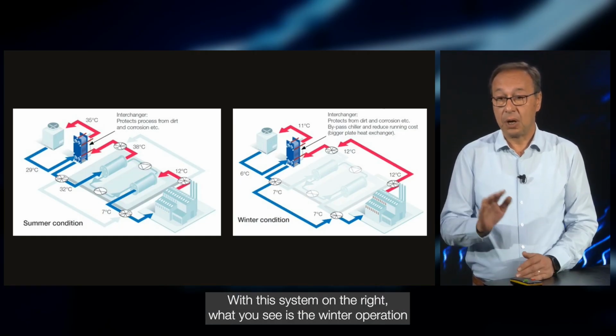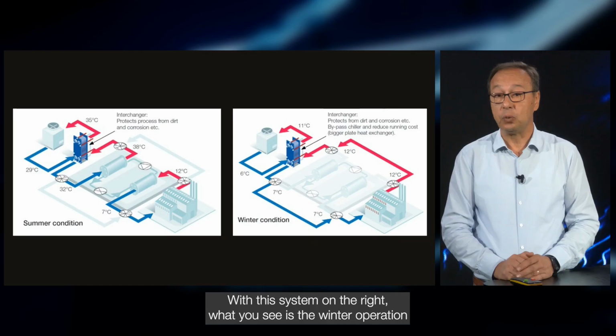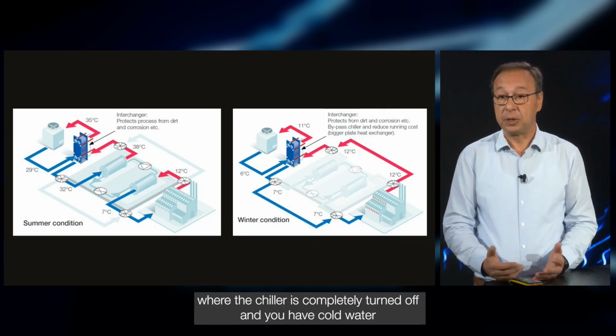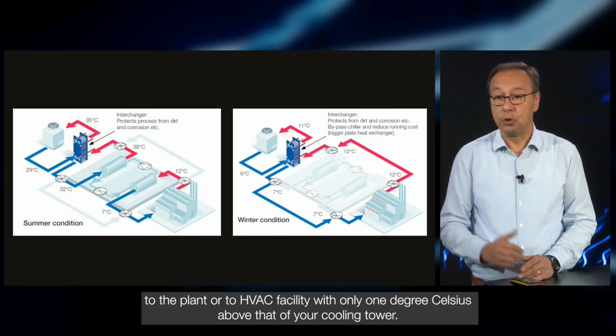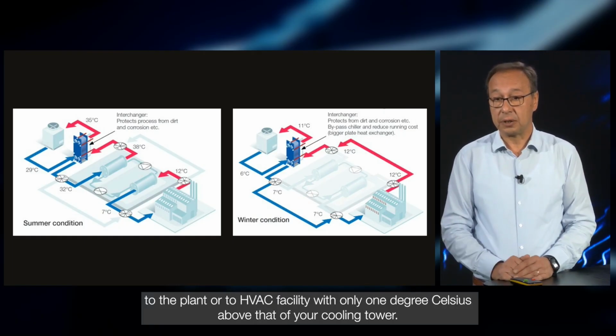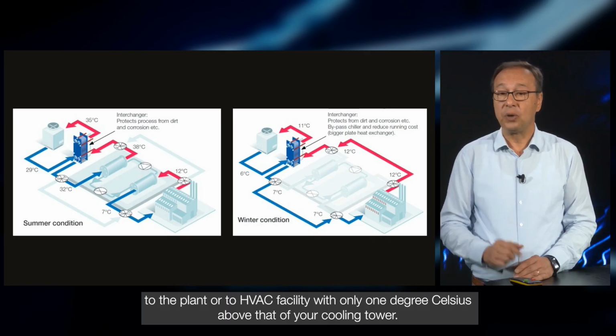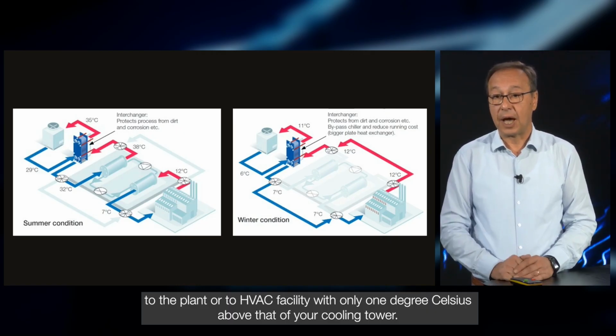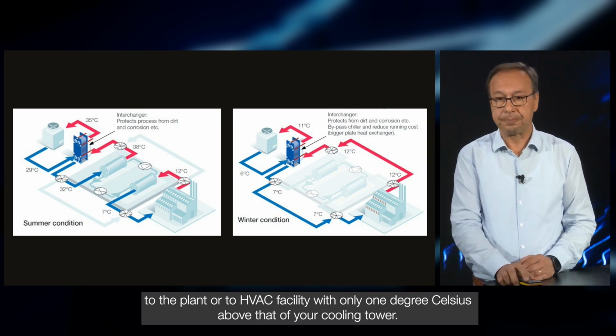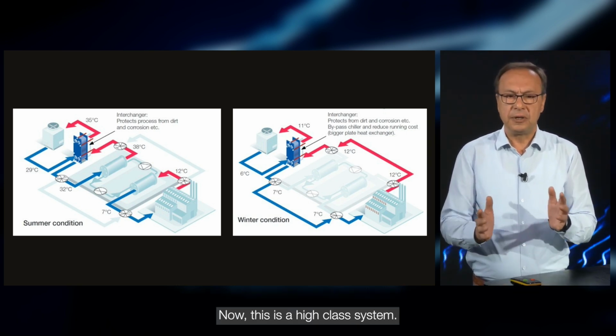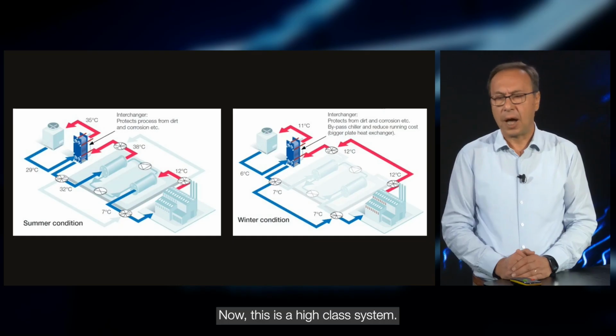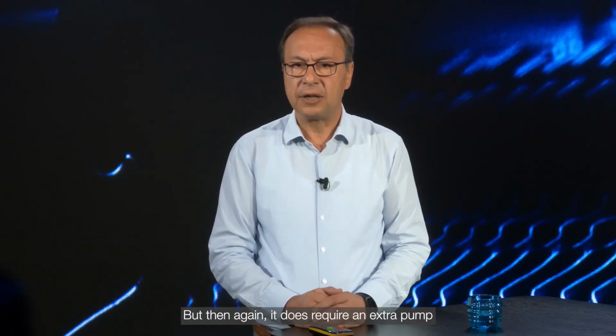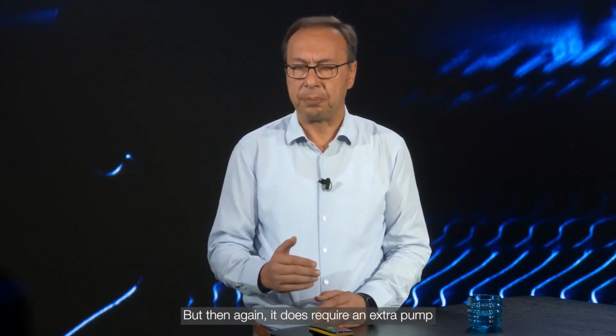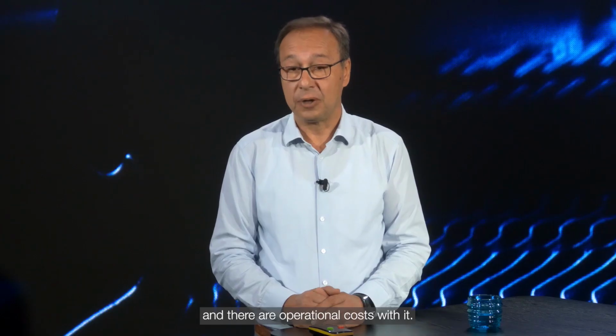On the right is the winter operation, where the chiller is completely turned off, and you have cold water to the plant or to the HVAC facility at only 1 degree Celsius above that of your cooling tower. Now, this is a high-class system. It's the best that you can put in, but it does require an extra pump, and there are operational costs with it.